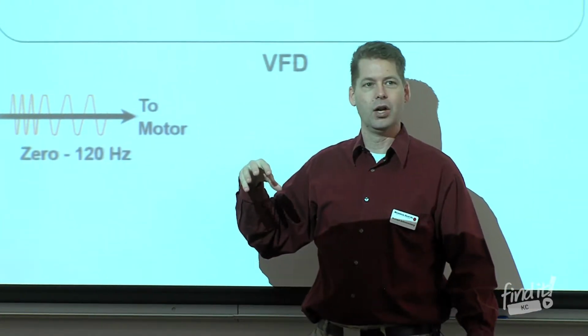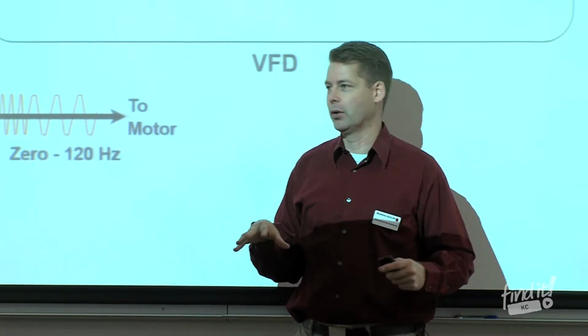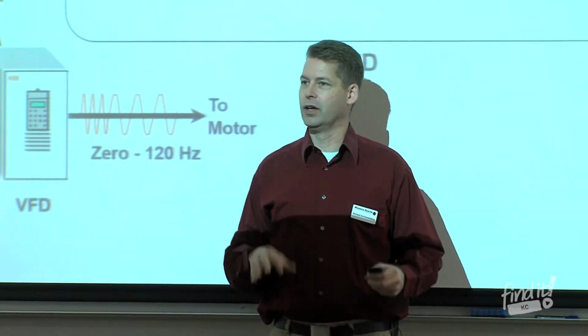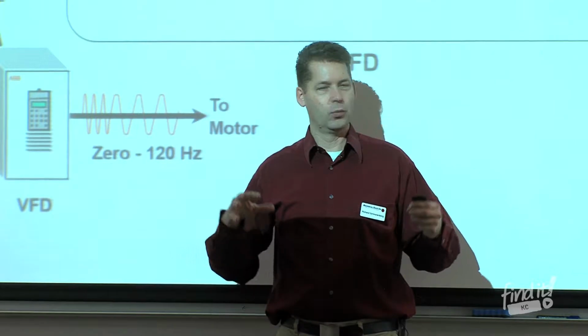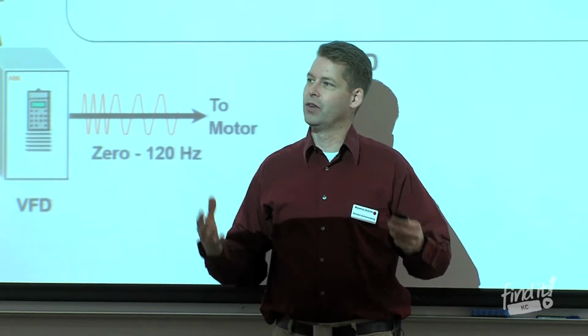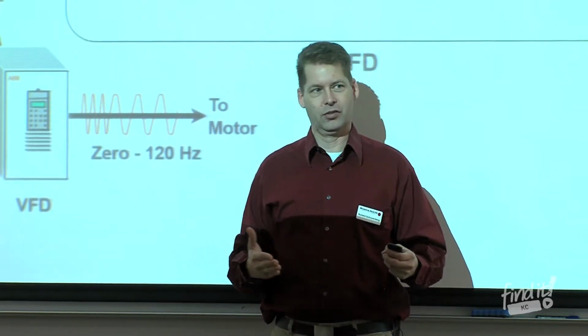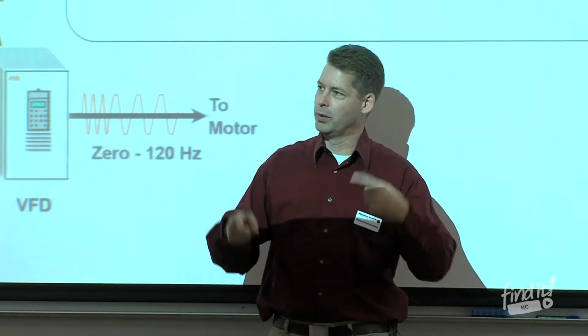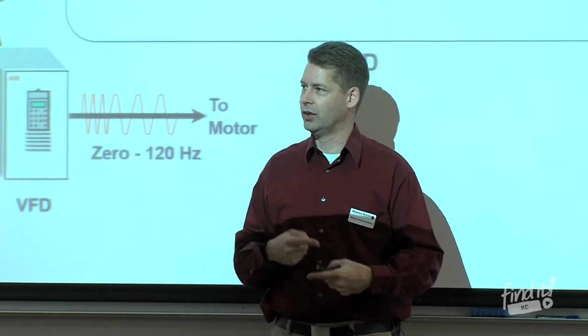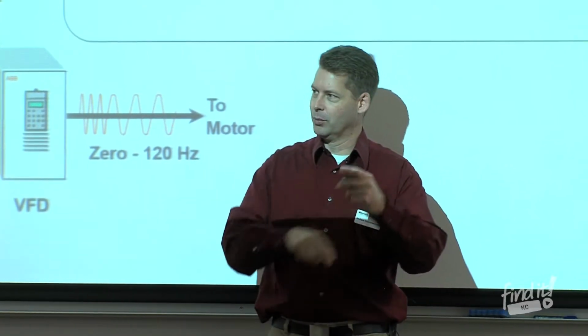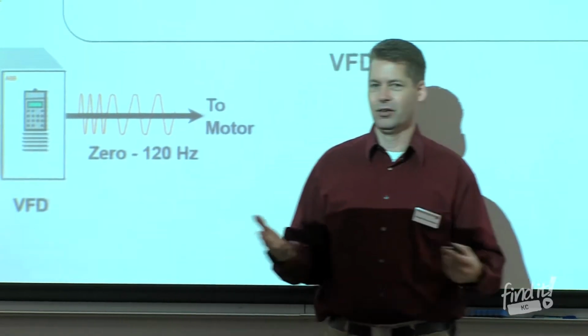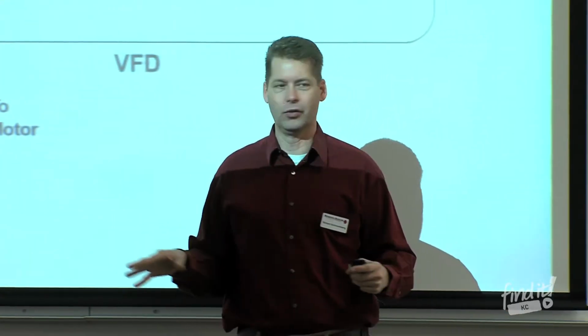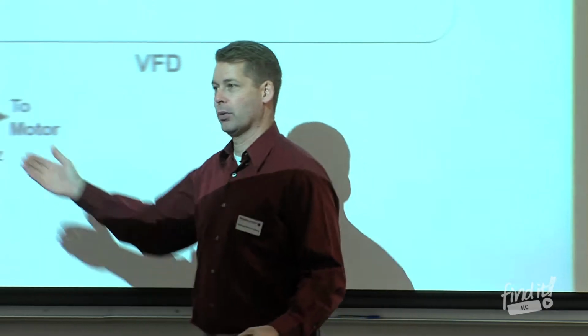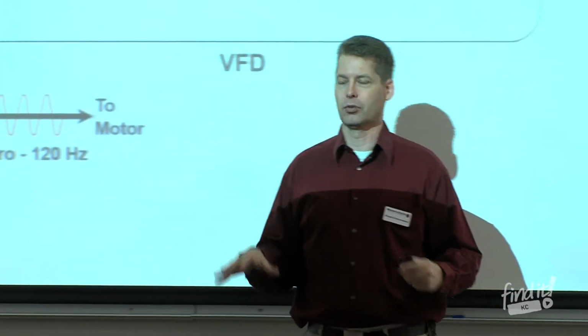That's a good point that the VFDs in the modern world right now, they're all running 3-phase motors. There aren't very many manufacturers of single-phase motor VFDs because it's kind of hard to make a single-phase motor spin the proper direction using VFD technology. 3-phase gives you the ability to control the speed, but single-phase out is a very small market and most VFD manufacturers don't play there. No problem bringing single phase in, but we're always running 3-phase motors.